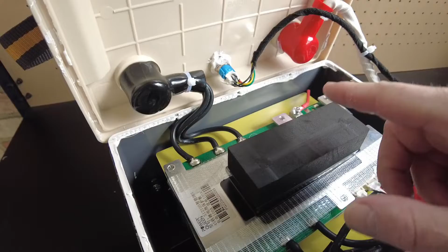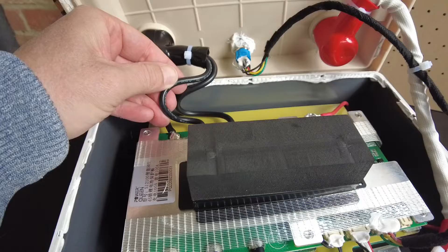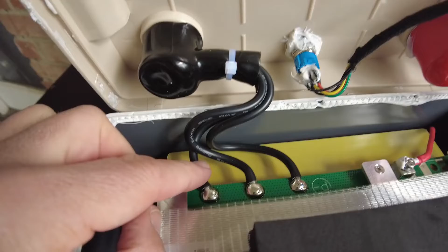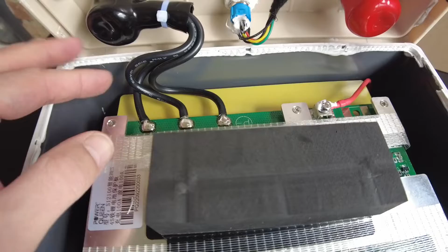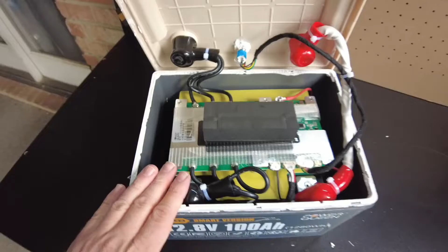We've got 3 silicone covered 10 gauge wires. Normally 10 gauge would be good for 30 amps, so 3 of them would normally be good for 90 amps. However, with silicone insulation, these wires can handle more heat. I think what I'd want to do is charge this battery back up, pull 100 amps, and check the temperature on these.